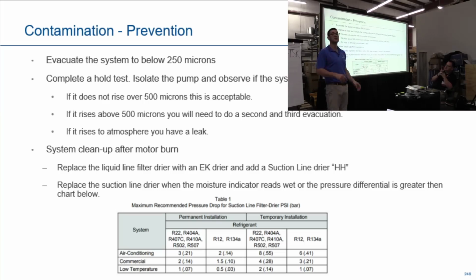If it rises all the way up and goes to atmosphere, well, then you probably have a leak in the system. If it rises up a few microns and stays below 500, you have a tight system. Okay. System cleanup after a motor burn. Well, use an EK filter dryer. So we sell filter dryers, premium filter dryers. But if you have a bad burnout, you might have to add a suction line filter dryer.